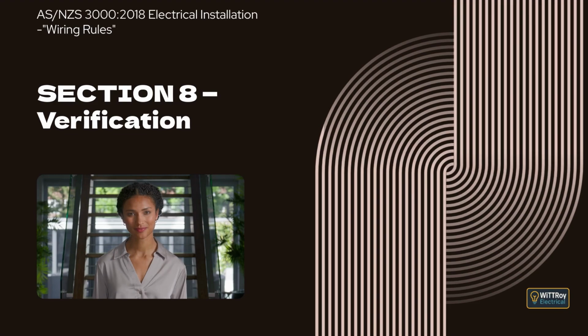Electrical installation conditions are checked, along with the correctness of wiring connections and protection against external influences. For switchboards, the inspection includes checking the location to ensure safe access and egress. Protective devices are reviewed to confirm correct selection and settings so they comply with overcurrent protection, arc fault protection, and discrimination requirements. Isolating devices such as main switches are checked, along with connecting devices like neutral bars, earth bars, and active links. The inspection confirms that wiring and switchgear are properly connected and fixed, that equipment is clearly identified and labeled, and that protection against external influences is provided.